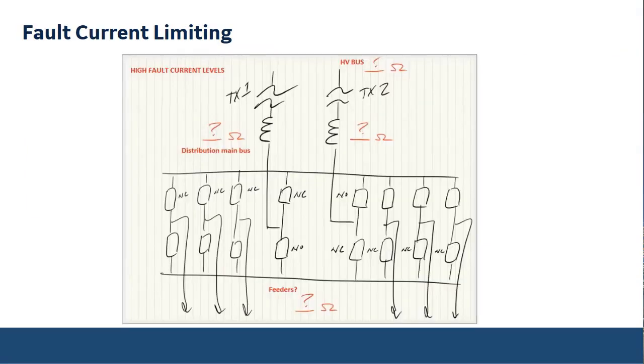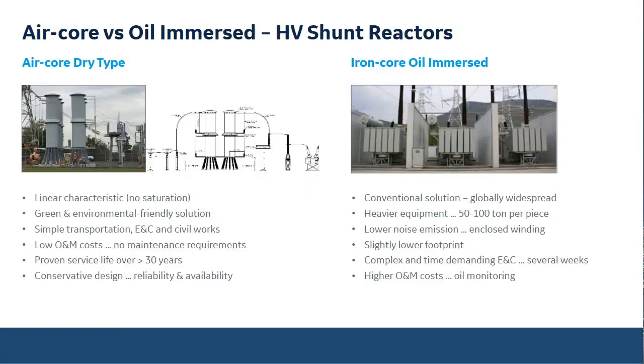So this is just an example of a main bus feeder reactors study, and whether it would make sense to put them on 13.8 kV feeders, for example, or on the main bus, let's say a 130 kV bus. So I would like to spend a little bit of time on the high voltage shunt reactors.